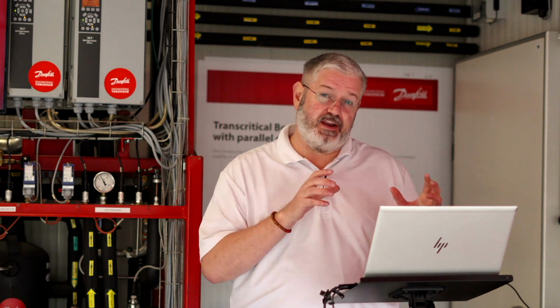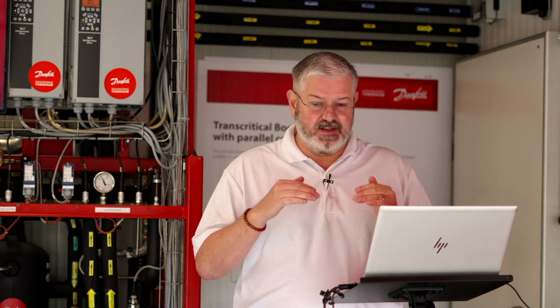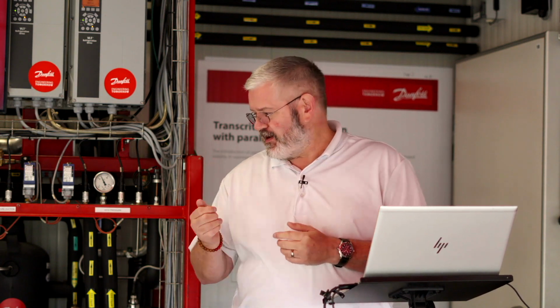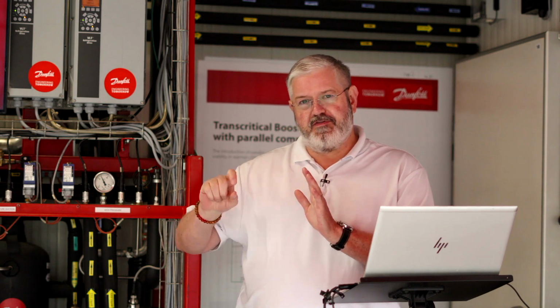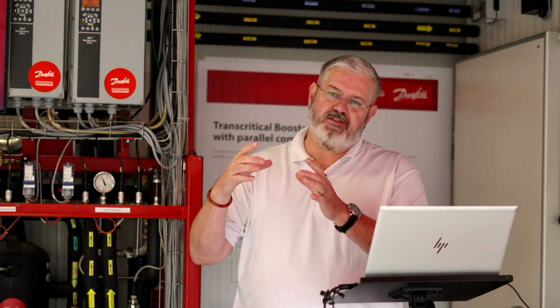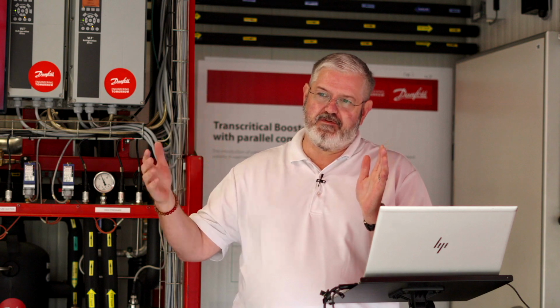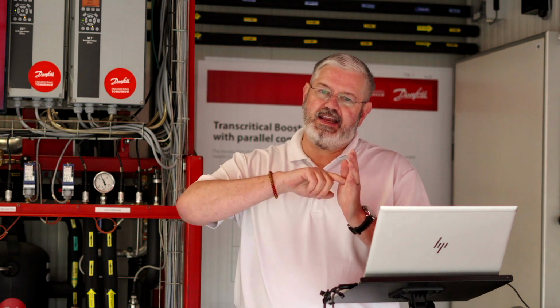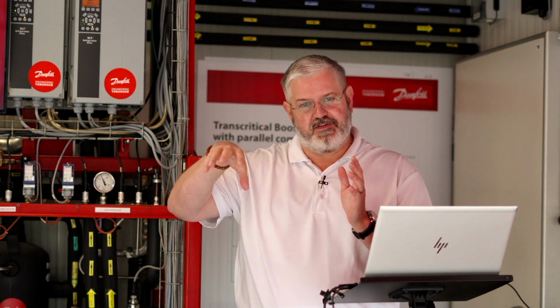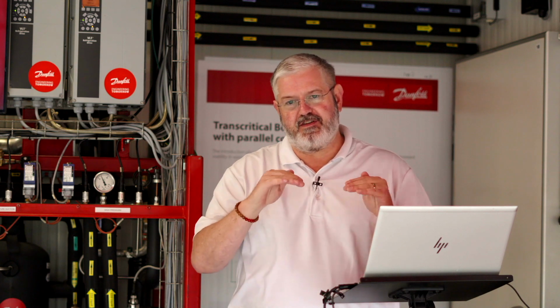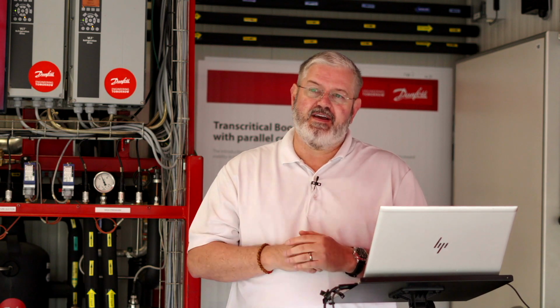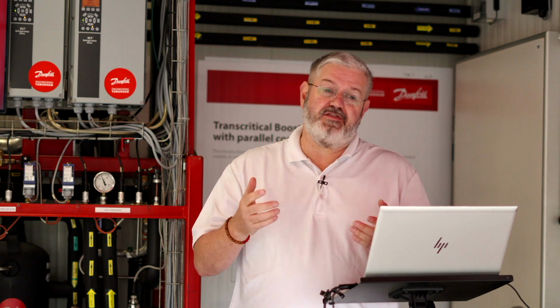Some customers will put a small condensing unit in a heat exchanger, so literally just to pull heat. So if you think of we're venting through the receiver valve, they can put a heat exchanger between the flash tank and that receiver valve, and they can take any heat buildup and run it off of a small condensing unit in a heat exchanger to manage that. That still requires that you have some type of auxiliary power. And then the other thing is that it just vents the charge.